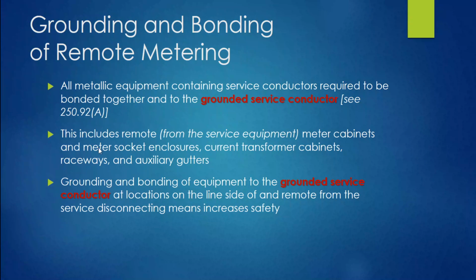That same level of bonding that is required in 250.92(A) is still here. Don't get into a false sense that it's not associated with anything like the service equipment. It is still got service conductors in it. So keep that in mind. That's the thing that you always want to remember. Keep in that loop of safety when it comes to grounding and bonding. Now, this includes remote from the service equipment, meter cabinets, meter socket enclosures, current transformer cabinets, raceways, and auxiliary gutters. All of those things fall into this.